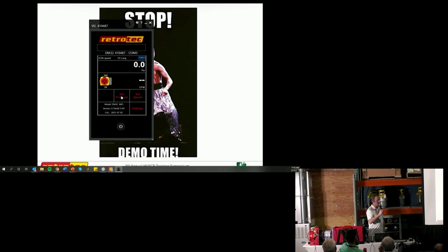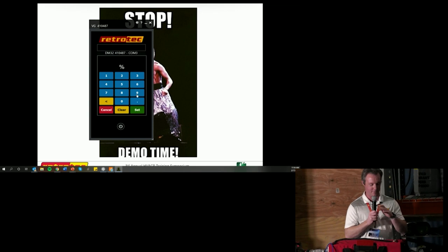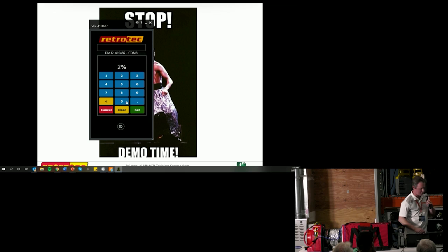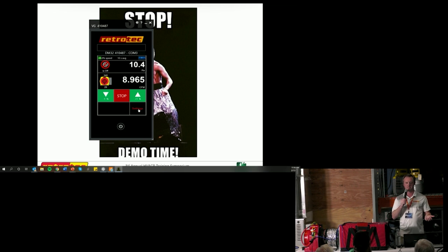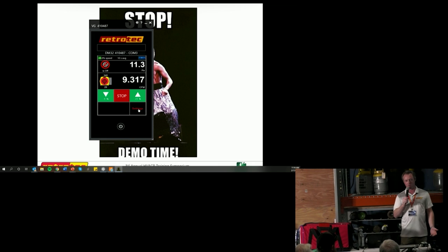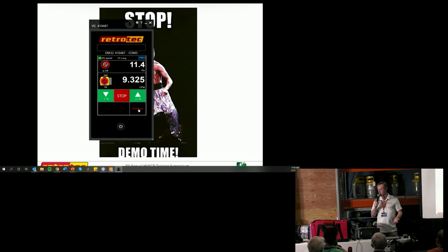The biggest takeaway is: when you leave, if you're not looking at the building envelope, you're missing about half of the equation. It's not always the HVAC system — the building envelope is a part of that HVAC system; it's containing all of that conditioned air you're working so hard to create. This is also where smoke can really help out. We'll fill this up so we can actually see the air leaks. As Allison Bailes has written, the blower door number doesn't tell us everything — when we shut doors, the HVAC system can actually exaggerate leaks in certain parts of the house even harder. When we shut doors and the air is not balanced, that air has got to go somewhere.